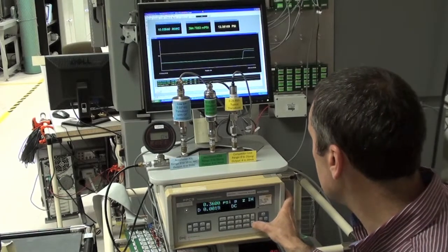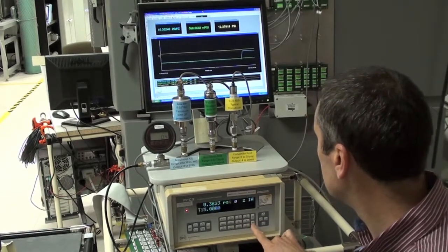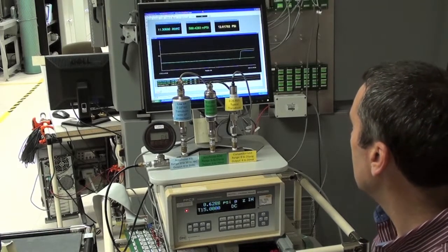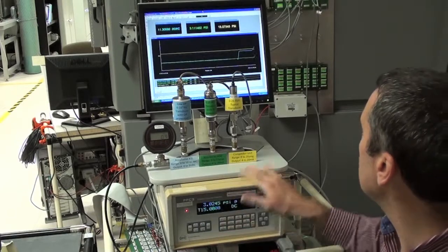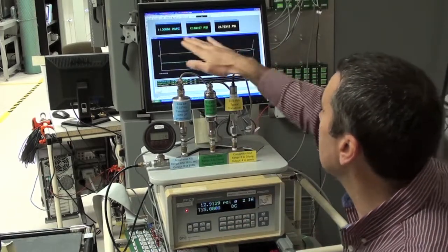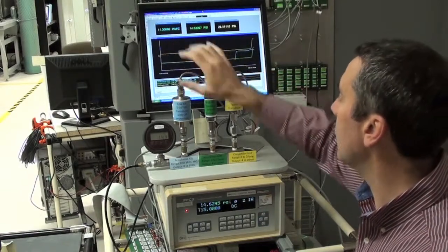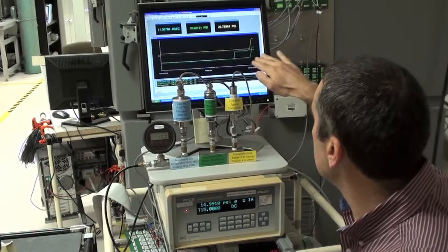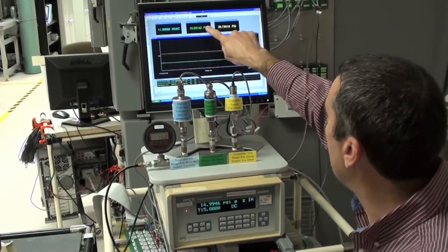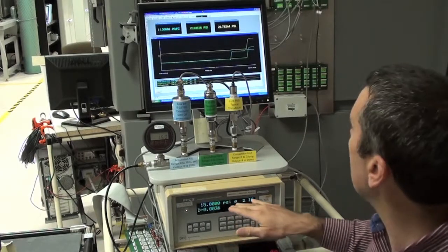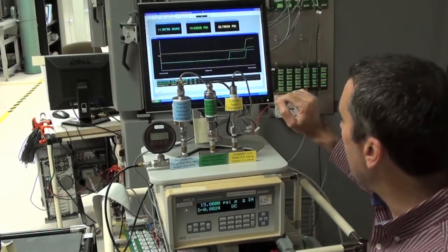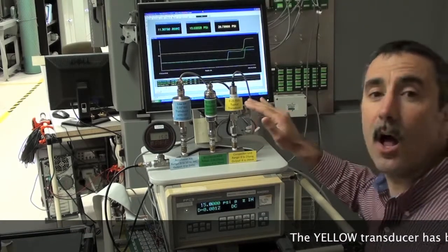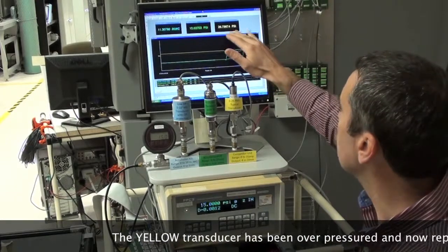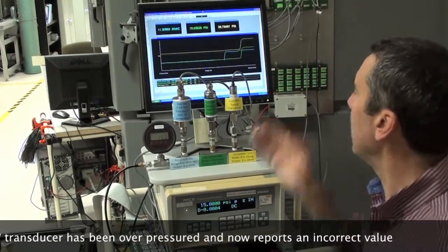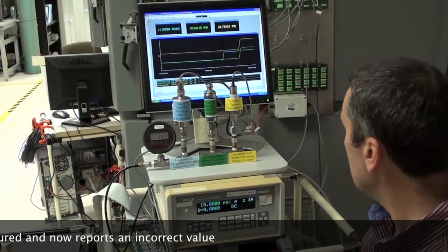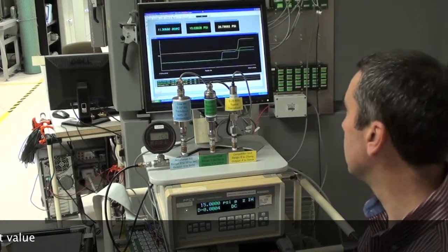I'm going to now change this to 15 psi. And now you can see the pressure's rising. The differential pressure transducer, it's already clamped at 11 inches. That's the most pressure it's going to record. The output is clamped. But the pressure is continuing to be recorded now by the 15 psi unit. You can see it's starting to stabilize at 15, and there it is, 15 psi. This other unit that's at 25 psi, it had already been overpressured, and you can see it's falsely recording 26.8 psi on the meter when in actuality it's only 15 psi.